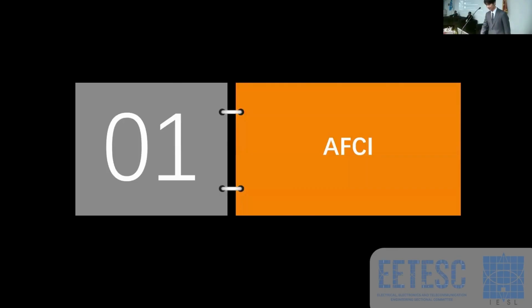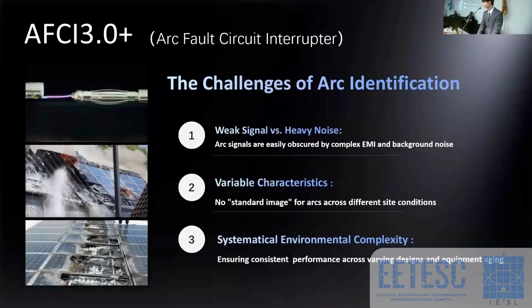Okay, so the full name of AFCI is arc fault circuit interrupter. When a circuit is damaged, the current will literally break through the air and intensify the flow of energy. This process will generate massive heat, so that will be the spark that leads to fire. Actually, DC arcs are the main reason of PV fires. With thousands of connection points in a large C&I PV plant, if there were no advanced technologies, it's impossible to stop the DC arc fault.